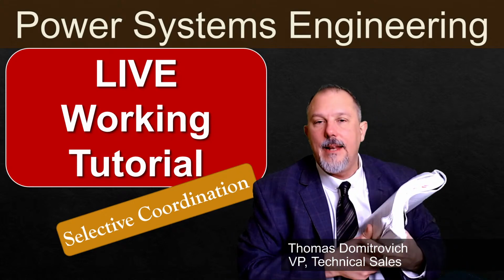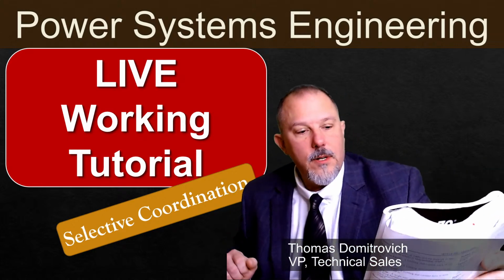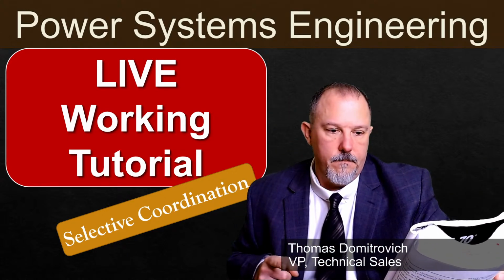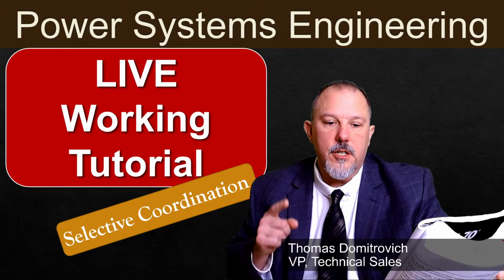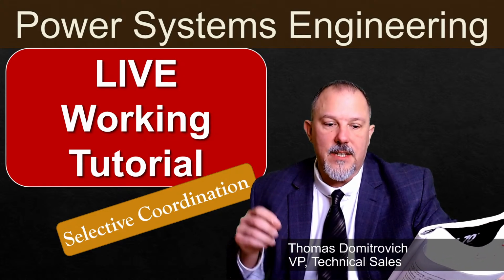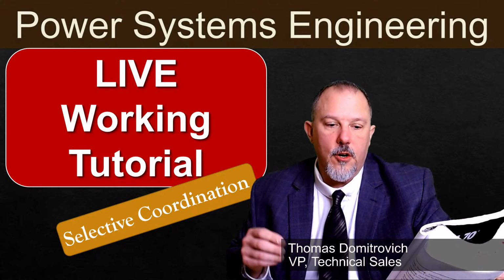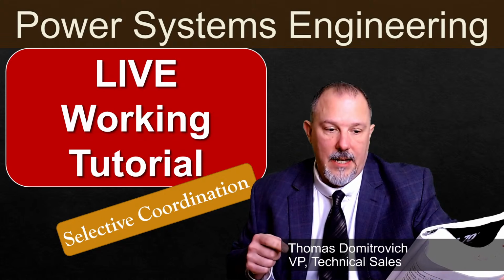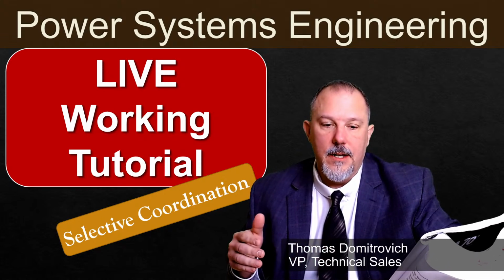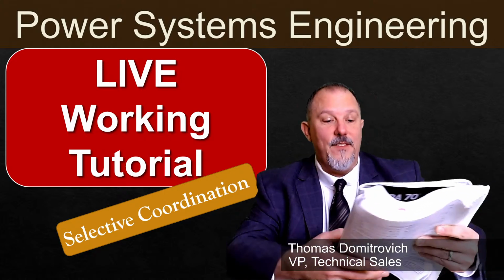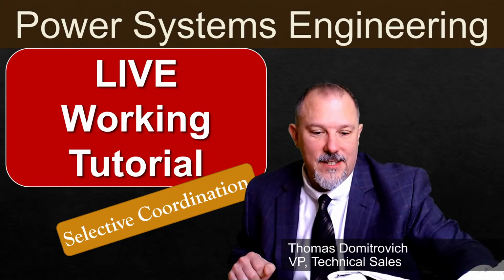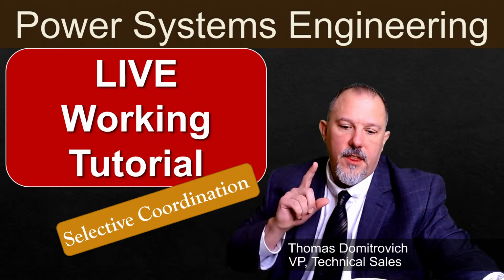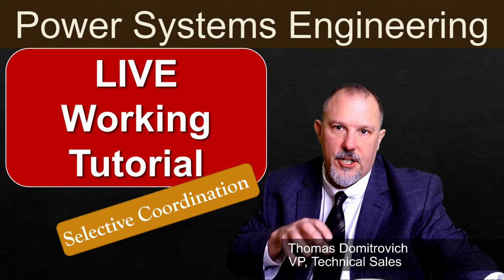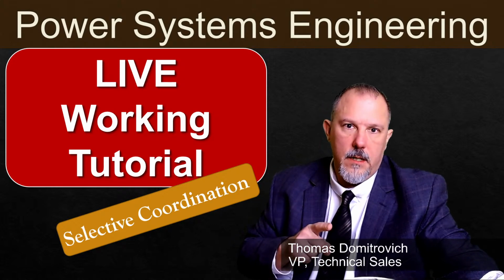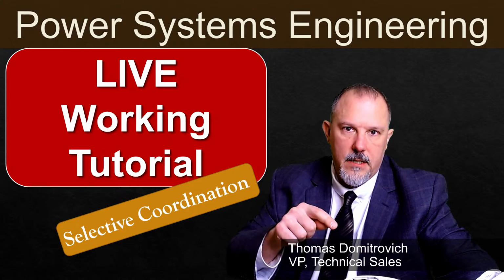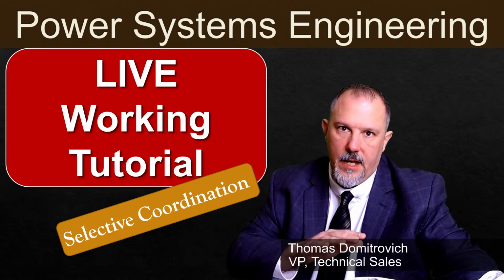Coordination, selective coordination. It says: localization of an overcurrent condition to restrict outages to the circuit or equipment affected, accomplished by the selection and installation of overcurrent protective devices and their ratings or settings for the full range of available fault currents. This is the longest sentence I think I've ever seen. Let's break this down a little bit. The first part is localization of an overcurrent condition. What does that mean? That means that the overcurrent protective device closest to the fault opens and nothing else.